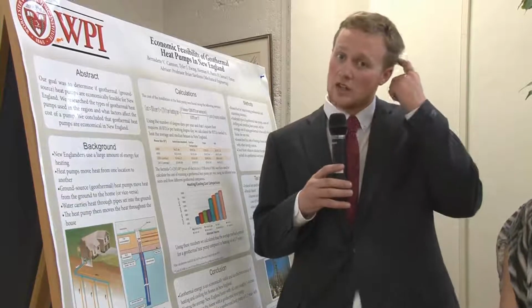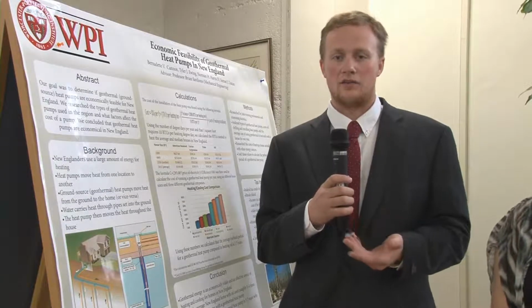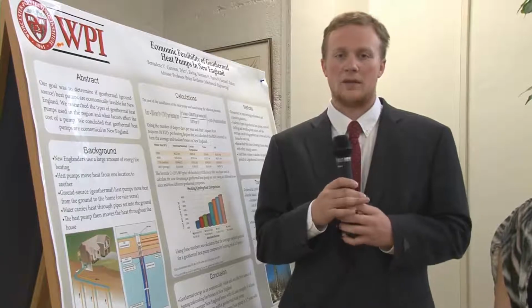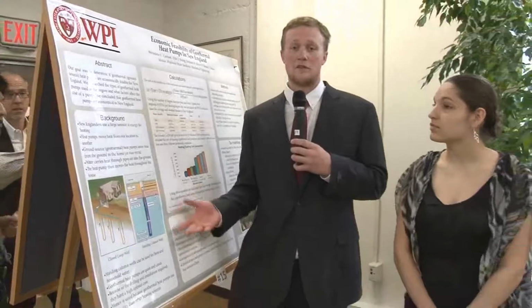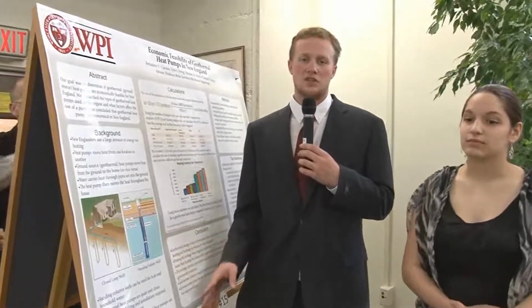high upfront cost for drilling. It's about $15 to $17 per foot, and typically the average home needs about 500 feet of borehole. So you can see that's a pretty high cost to drill. Not only drilling, but you need to renovate your house if it's an existing home. That, again, is like another $13,000, depending on what you use as your heating, whether you use forced hot air, forced hot water, or electric. Typically, it's easy to convert to forced hot air because that's what the geothermal will use.